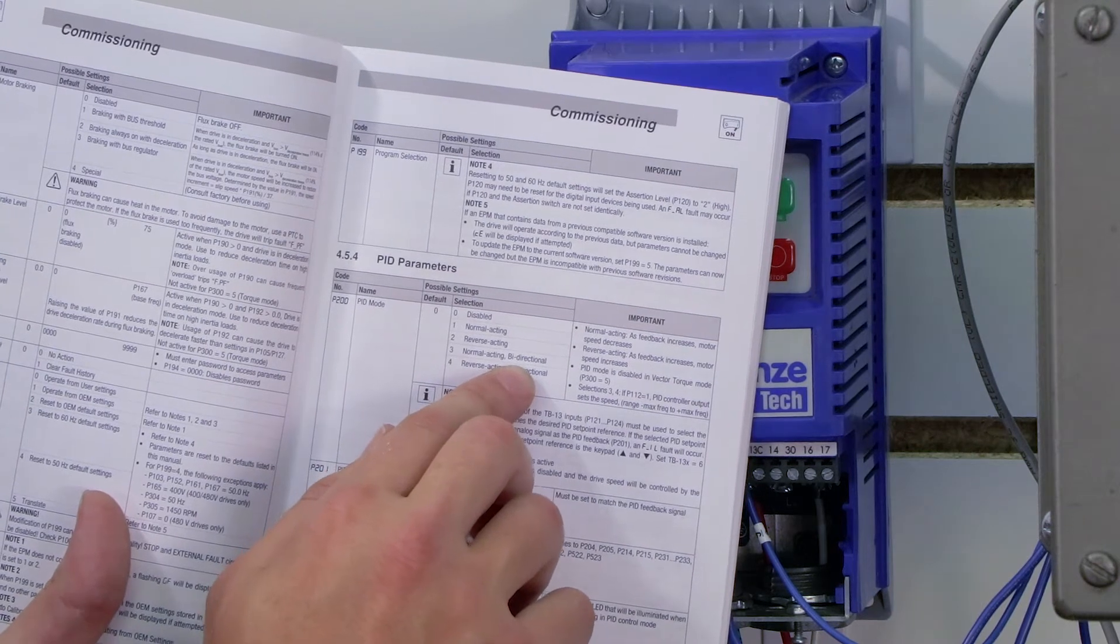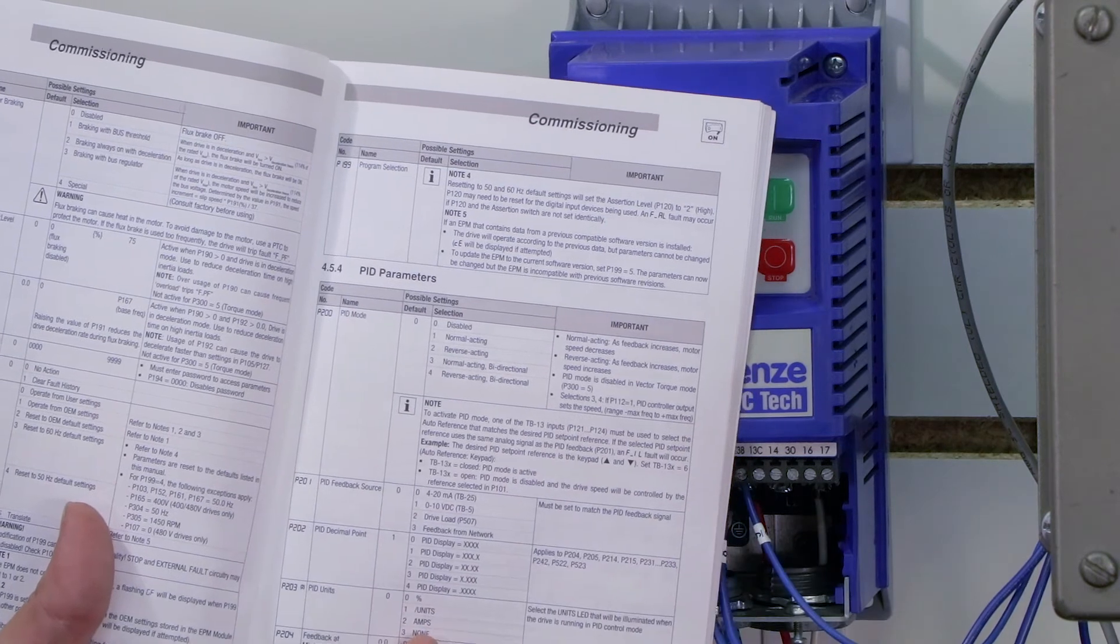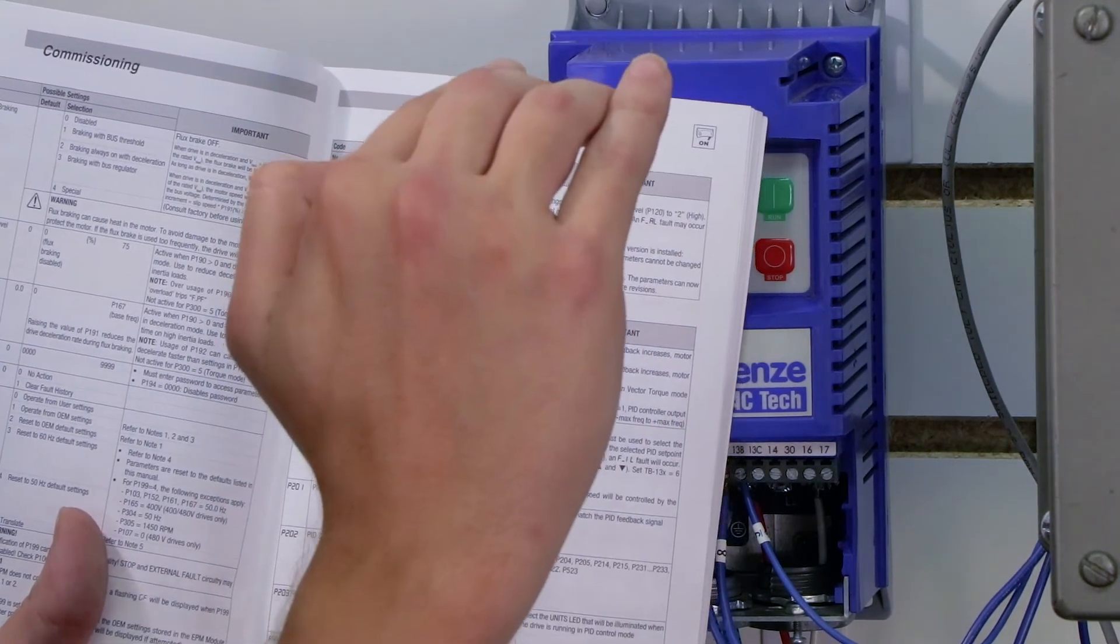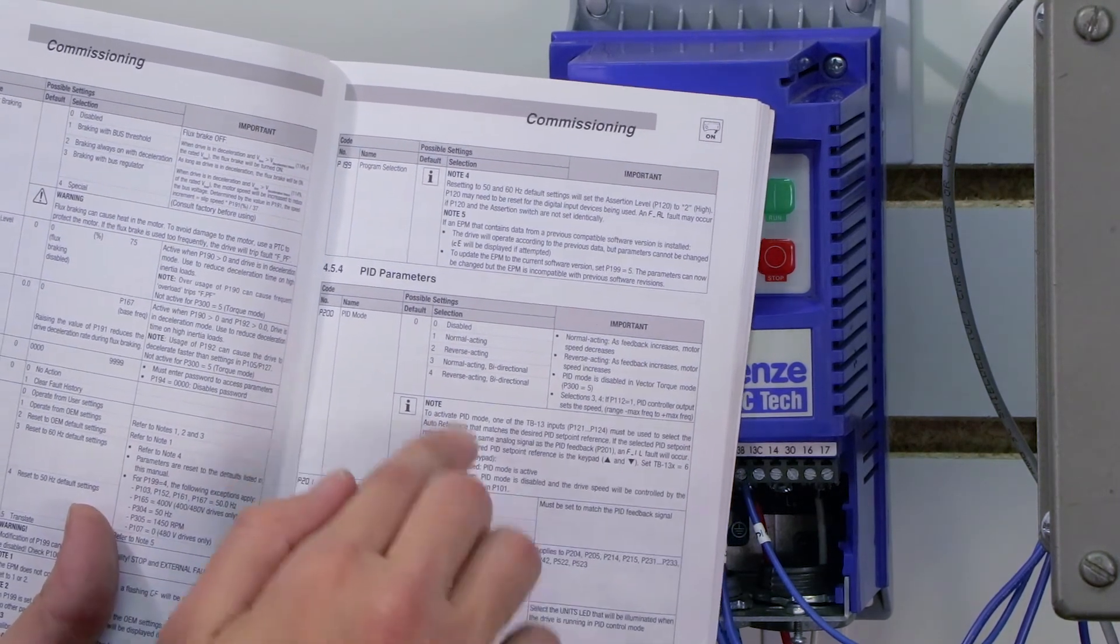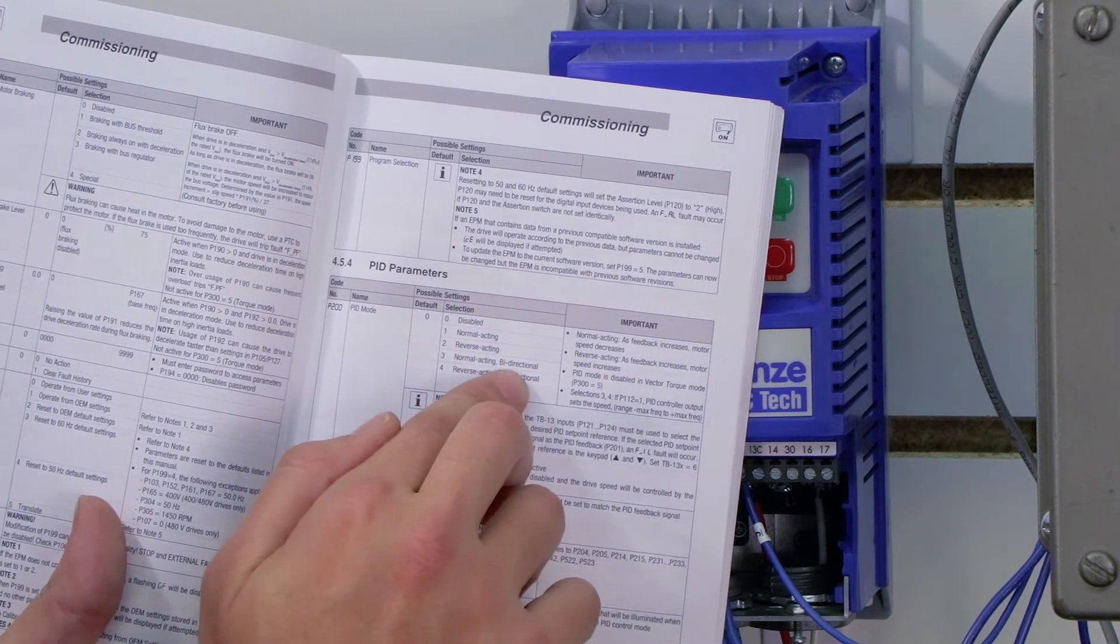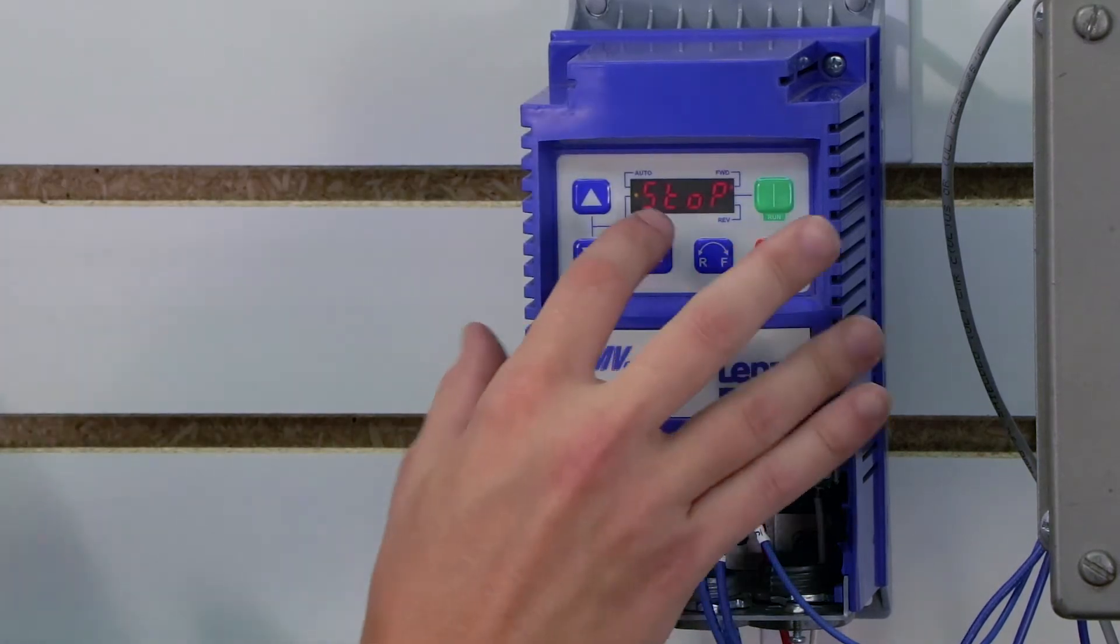Now I can also do normal acting bidirectional, which means that if for some reason my signal goes in the opposite direction from my set point, in other words, if I overshoot, maybe my tank gets too full, and my set point's 50 and I get 70, I can actually have the motor run in the opposite direction to empty water. So that's one option as well. But in my case, I don't need it to try to empty water. I have a one-way pump. I don't have a bidirectional pump. So I'm still going to set mine to normal acting.